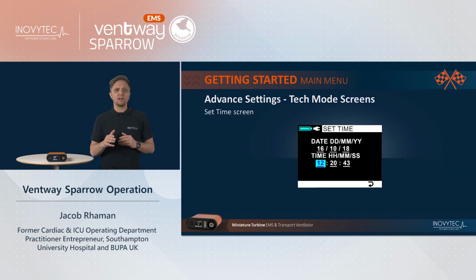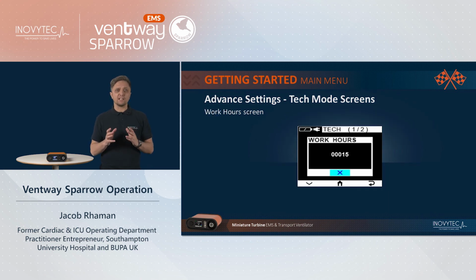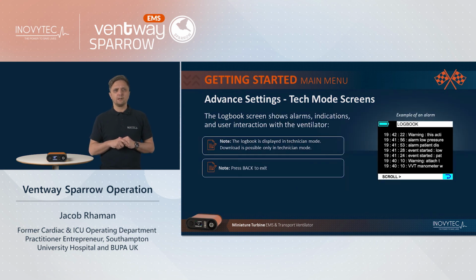You can set the time and date using the navigation wheel and pressing the knob. You can also access work hours. This screen will give you the total amount of hours that the ventilator has been in active use. At 1,500 hours, the ventilator must be serviced. And finally, the logbook screen shows alarms, indications, and user interaction with the ventilator.